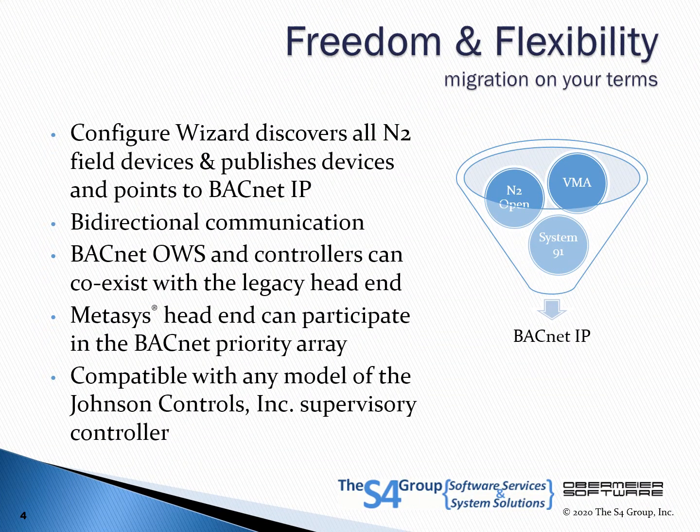S4 Open appliances support any N2 device installed on a BAS currently supported by Johnson Controls and any Metasys supervisor controller with N2 protocol support. S4 Open appliances are the only product that allows coexistence with the legacy Metasys supervisor controller and operator workstation. This can be utilized to support transitions in critical environments or to have the S4 router act as a data collection agent for value-added applications without impacting legacy system operation.